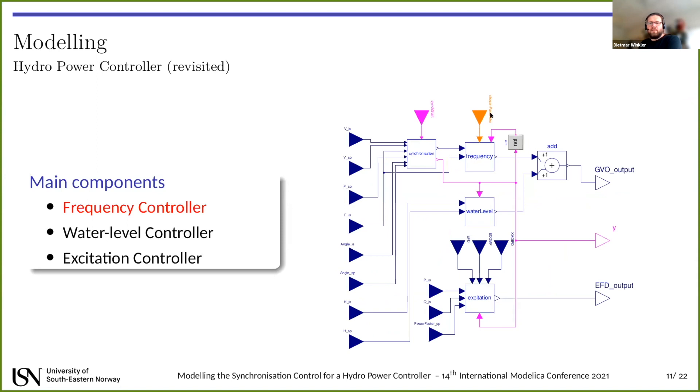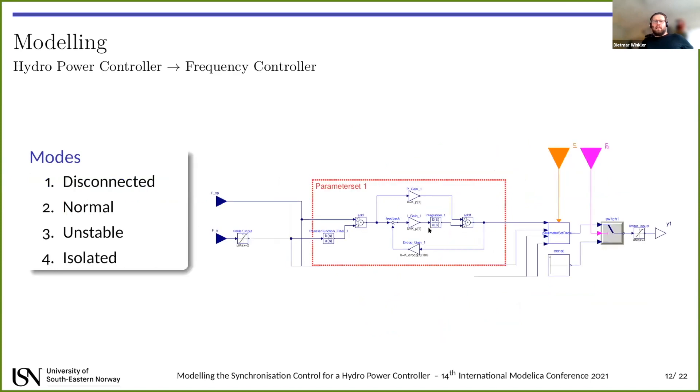The next part inside the hydropower controller is the frequency controller. This frequency controller takes in the synchronization signal and also the frequency and gives out the guide vane opening. It has different modes. Basically the modes are disconnected, normal, unstable, and isolated, depending on how your generator is connected. Is it disconnected? Is it in normal operation? Is it providing an isolated load? Or is it some unstable voltage scenario? The only difference between those different modes is that the internal PI controller, which is this one, has different settings for the gain. So you can switch between the different modes. There are several of those parameter sets implemented. This is just one way to do this. There are always several ways you can do this, but this is how the project has done it.